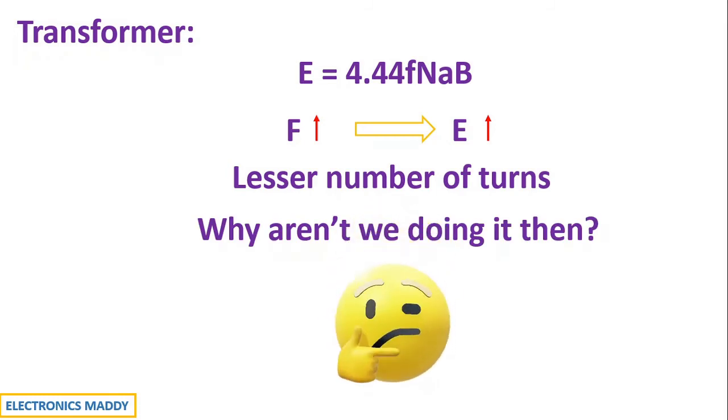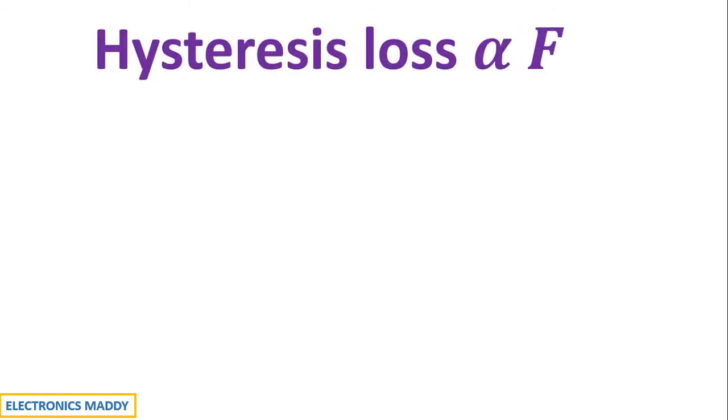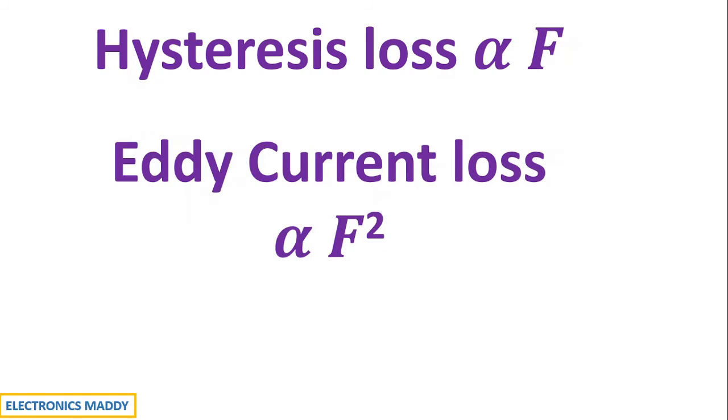It is because of the losses. Hysteresis loss in a transformer is directly proportional to frequency, whereas eddy current loss is directly proportional to the square of the frequency. Therefore, as frequency increases, the losses also increases and hence we go with an optimum value of frequency such as 50 Hz or 60 Hz.